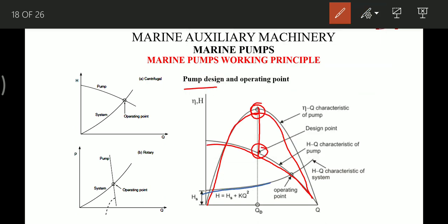Our main objective is to keep the operating point as close to the design point as possible to maximize pump efficiency. This can be done by altering conditions of the system — such as changing the pipe diameter, the pipe length, or the number of valves — to shift the operating point closer to the design point so the pump operates under efficient conditions.